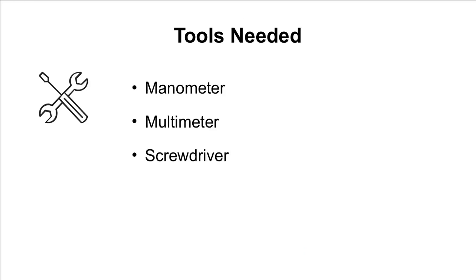For the basic troubleshooting, you will need for this unit a manometer, a multimeter that is capable of reading low voltage circuits, because this unit does have 24 volts AC and DC circuits. The multimeter will also need to be able to read DC microamps to test flame sense. The last thing you'll need is a Phillips screwdriver.